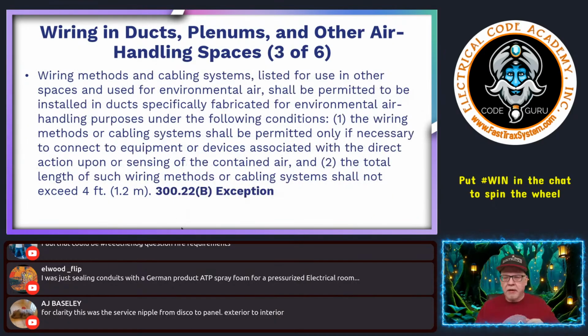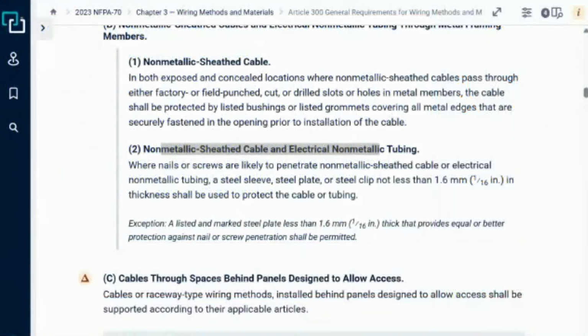Okay. Now, you have here wiring methods and cabling systems listed for use in other spaces and used for environmental air shall be permitted to be installed in ducts specifically fabricated for environmental air handling under the following conditions. So you have some allowances. Now I want to show you that in the code real quick, just so you can see how the exceptions work so that we get an idea. So let's go to the code.